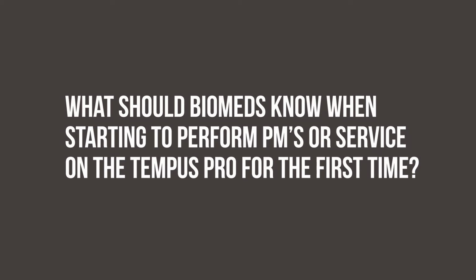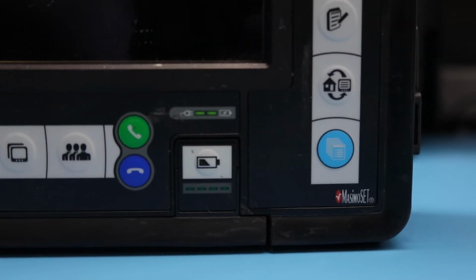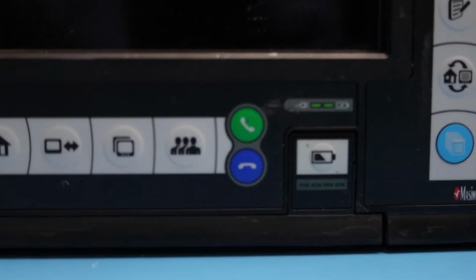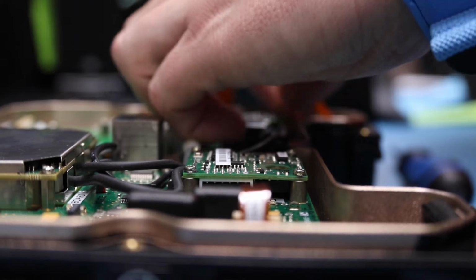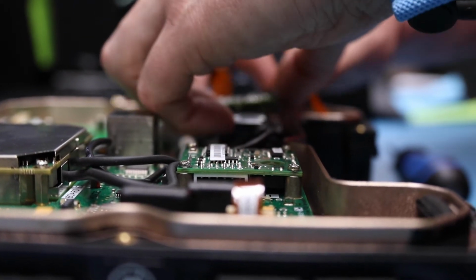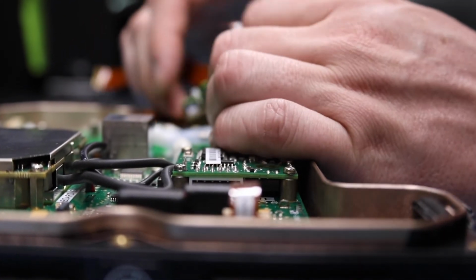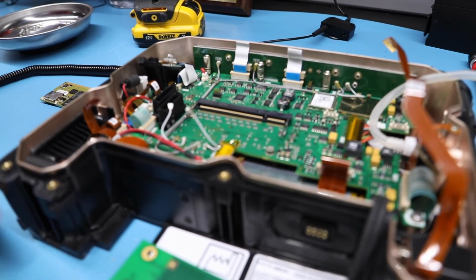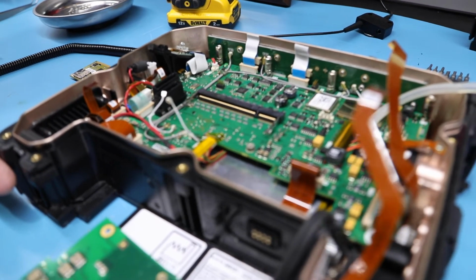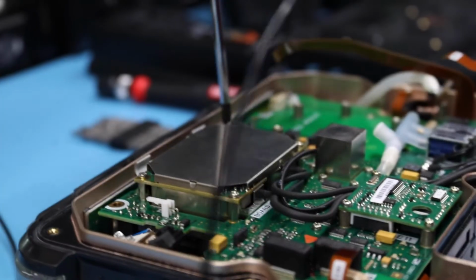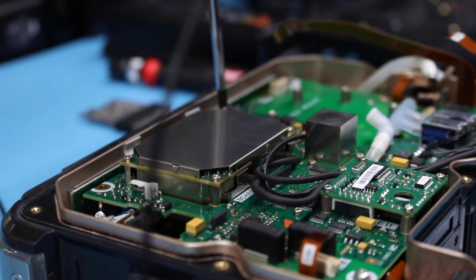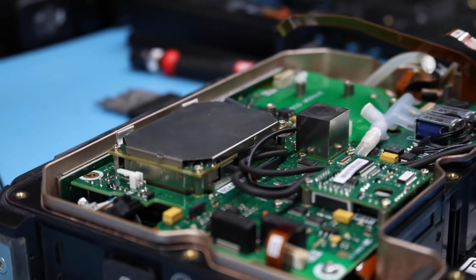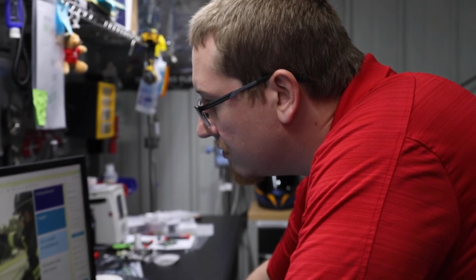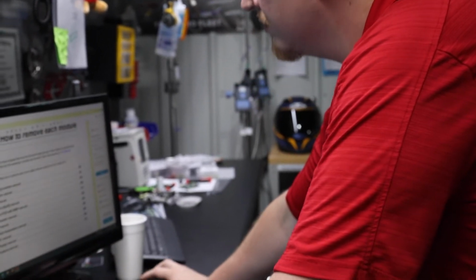The Tempus has very in-depth testing and calibration. These are attributable to the functionality of the unit. The Tempus has standard calibrations, such as CO2, IBP, and NIBP. However, it requires deeper testing than most monitors or DEFIBs. For example, the ECG function requires a USB file to be saved of the readings from each lead. These must then be examined to verify correct ECG readings produced by the calibrated test equipment.